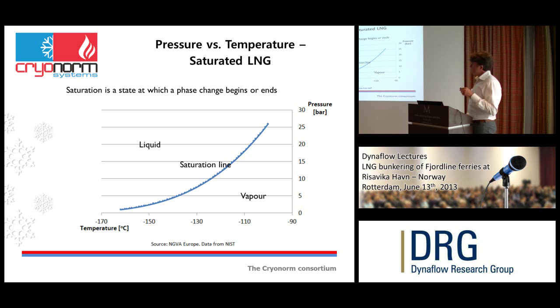The way you do that is you have your vapor sitting at 5.7 bar and your liquid sitting at 5.7 bar. The ship comes in, you attach the loading arm, and first start filling the top of the tank with LNG at about 1.5 bar, since it's coming out of an atmospheric tank, then brought up to 8 bar by the pump, but your LNG saturation still sits at 1.5 bar.